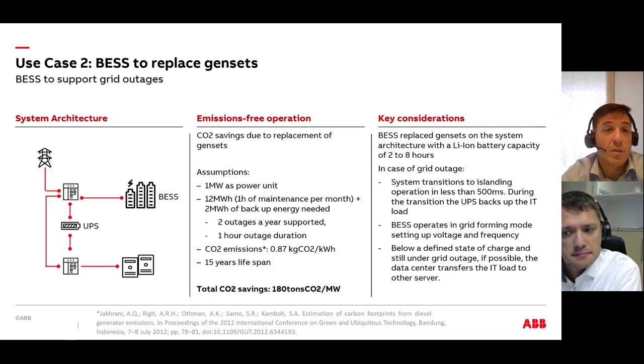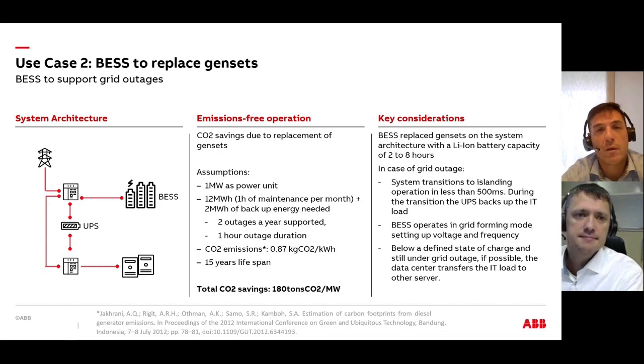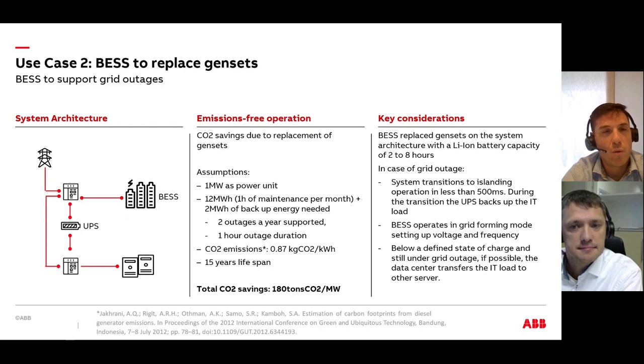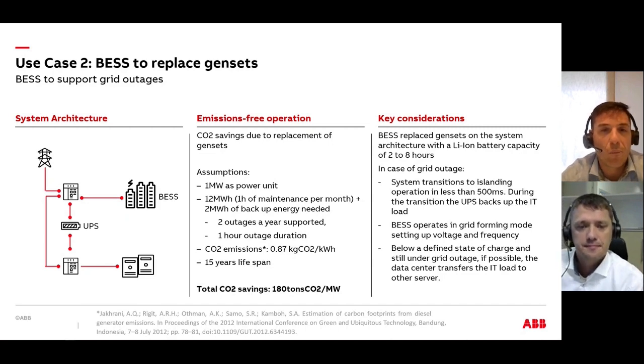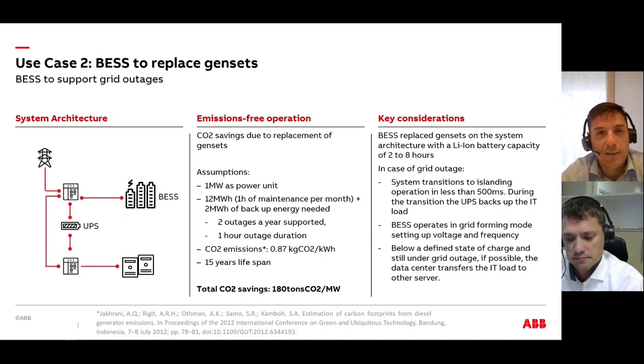In this case, of course, the consideration we have to bear in mind is that the capacity in the BESS is going to be much longer. Normally, we are considering between 2 and 8 hours duration. In case of grid outage, it's the same as before. The system is going to transition to island operation. The UPS is backing up the IT load during the BESS start. The main thing we have to consider now is that below a defined state of charge and still under grid outage, if possible, the data center has to transfer the IT load to another server because the batteries are running low and we are going to be offline at some point.